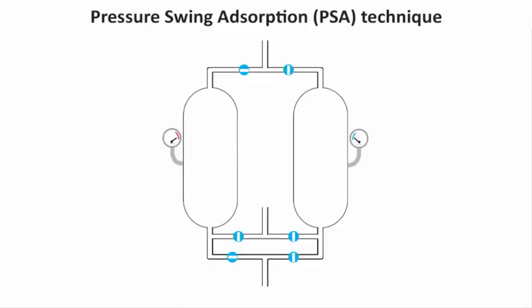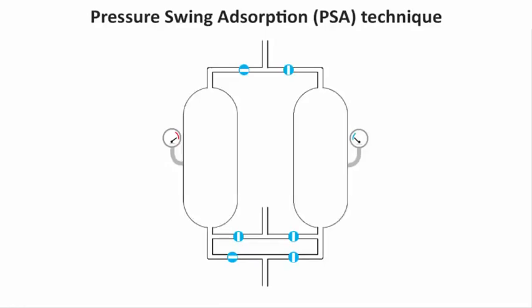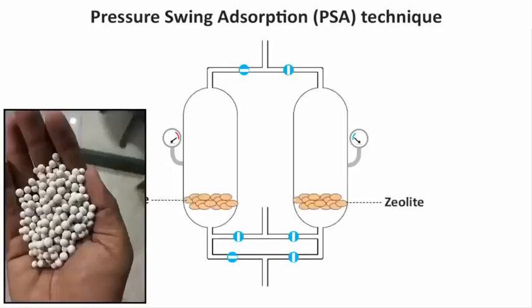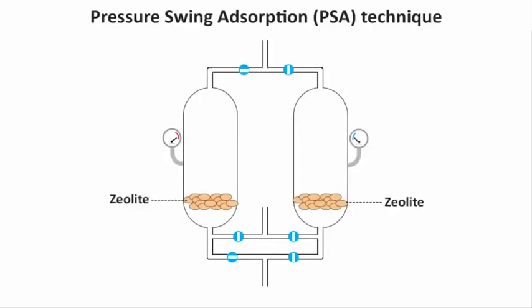Now let's see how PSA technology works. Two pressurized tanks or vessels are required, and at the bed level of these two tanks, zeolite pellets are placed to act as an adsorbent. The process starts when dry compressed air is blown through a valve into the first vessel, where the pressure inside the tank is built up to reach around 5 to 10 bar, or 70 to 150 psi.